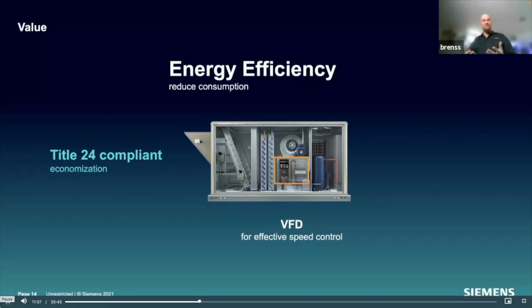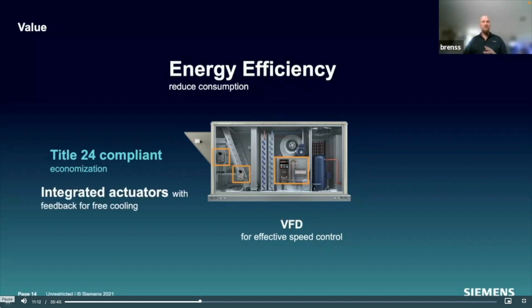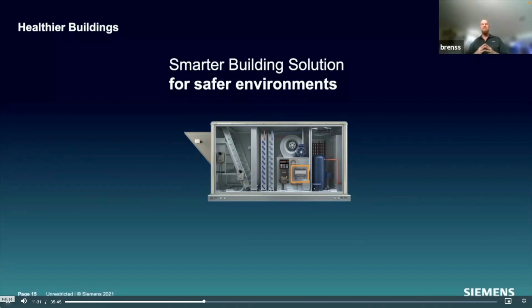The controller is also Title 24 compliant for economization, which means there's no use now for a separate economizer controller. Title 24 has been driving the solution for a long time, and now we have one built into the controller. Integrated actuators with feedback for free cooling will tell you always where your dampers are and when they need to be used. Let's talk about smarter building solutions for a safer environment.